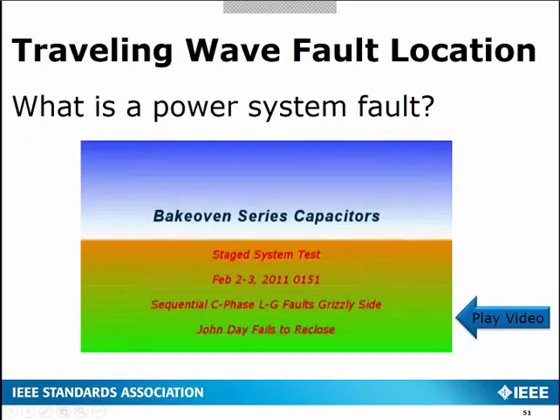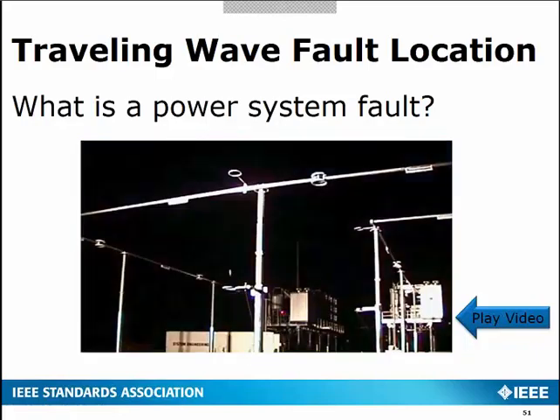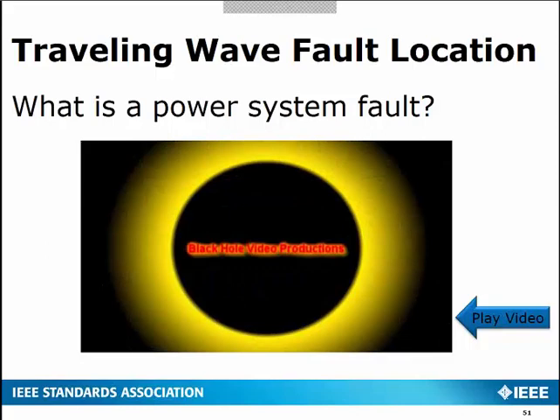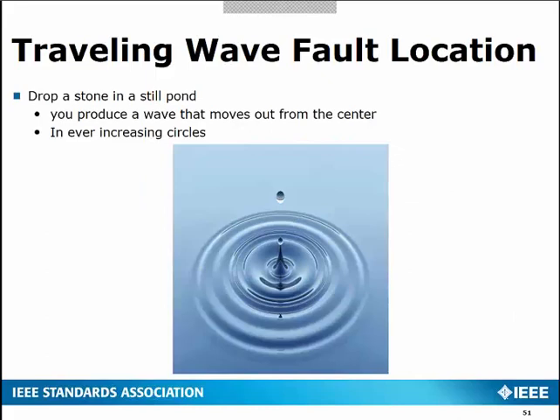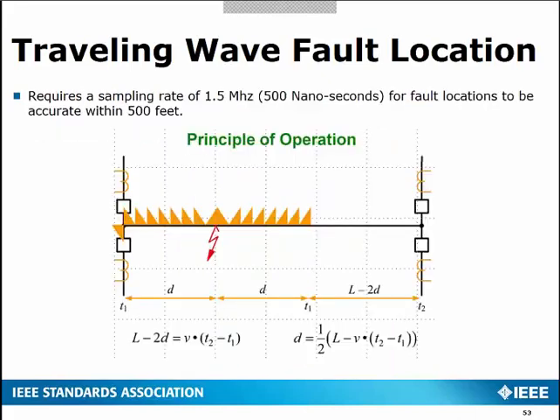The next type of application that we are starting to use is called traveling wave fault location. What exactly is a fault? A fault is when the line actually goes to the ground and it must be cleared. But during that time, when a fault occurs on a transmission system, it's very similar to a drop of a stone in a pond. There are high-frequency waves that travel throughout the power system in ever-increasing circles. These waves generally travel at close to the speed of light and need to be sampled at 1.5 megahertz to capture them. But by doing that with precise timing, we can determine where the fault occurred by comparing at both ends of the line.